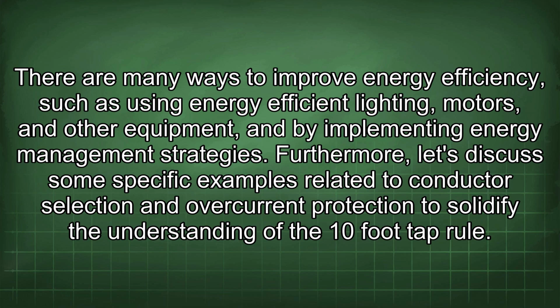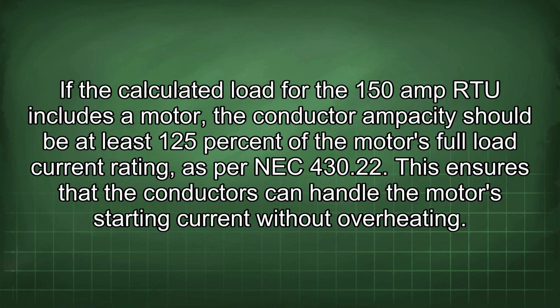There are many ways to improve energy efficiency, such as using energy-efficient lighting, motors, and other equipment, and by implementing energy management strategies. Furthermore, let's discuss some specific examples related to conductor selection and overcurrent protection to solidify the understanding of the 10-foot tap rule. If the calculated load for the 150 amp RTU includes a motor, the conductor ampacity should be at least 125% of the motor's full load current rating as per NEC 430.22. This ensures that the conductors can handle the motor's starting current without overheating.